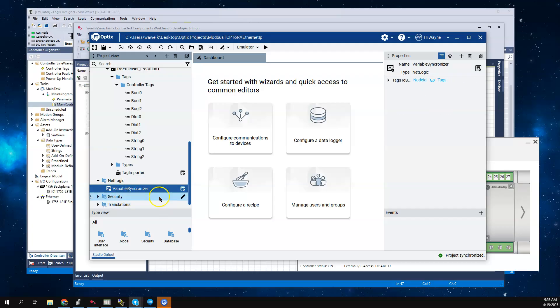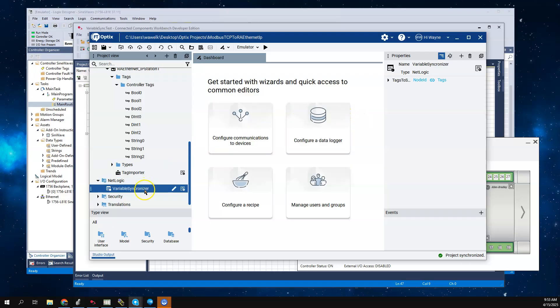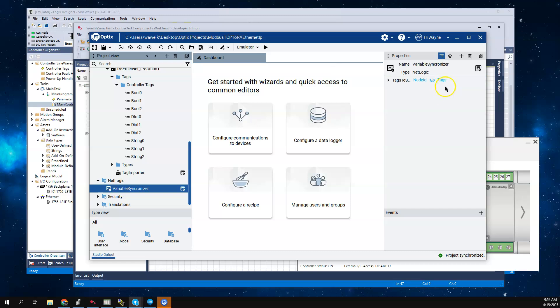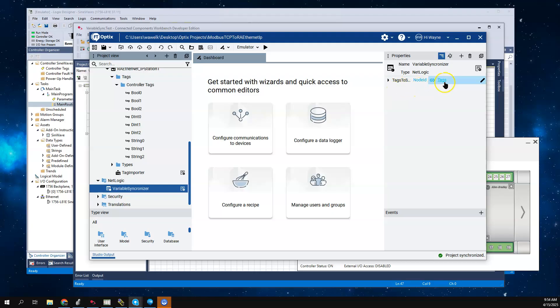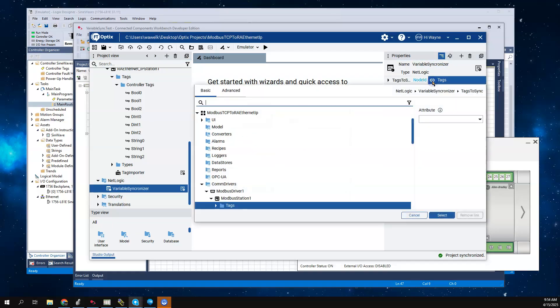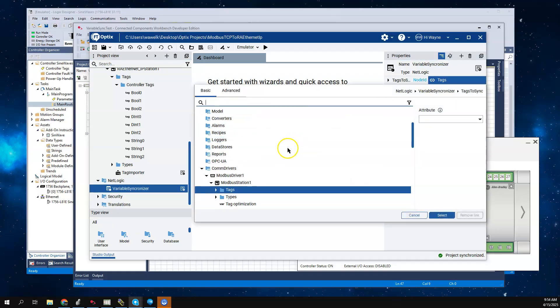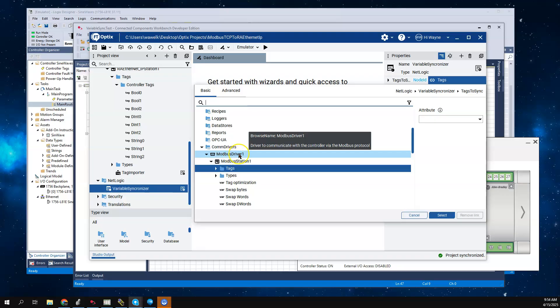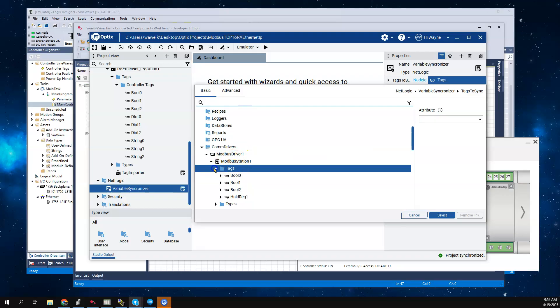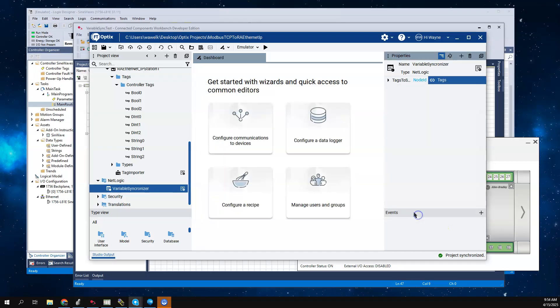If I click on this to get the properties, the way how this works is it's a parameterized C# program. All it wants to know is where are the tags that I'm going to synchronize coming from. It's basically tags to sync - that's what this identifier is called. If I click on the dynamic link, it's actually linked right to the Modbus driver in the tags folder.